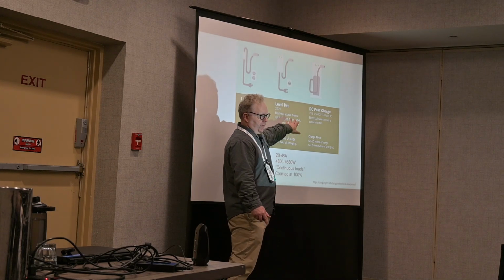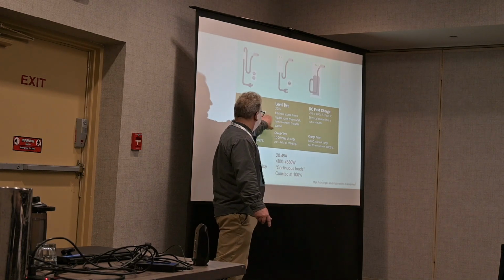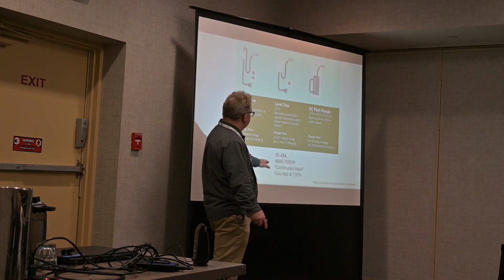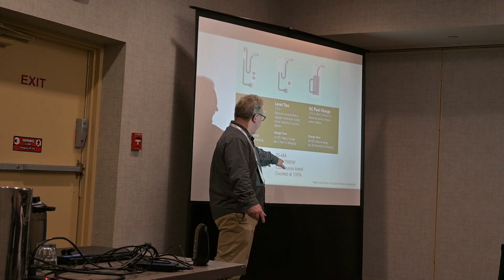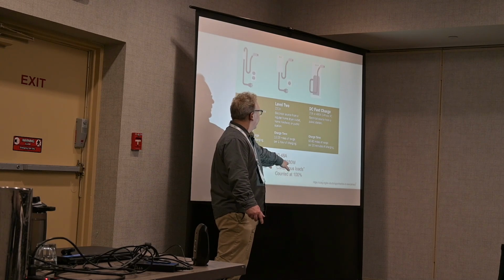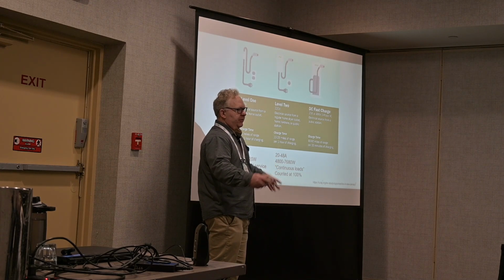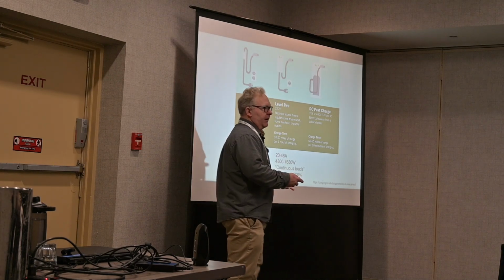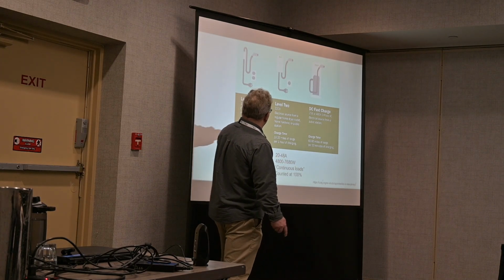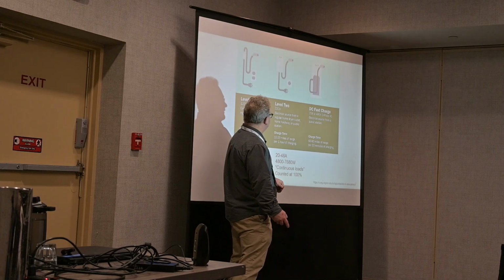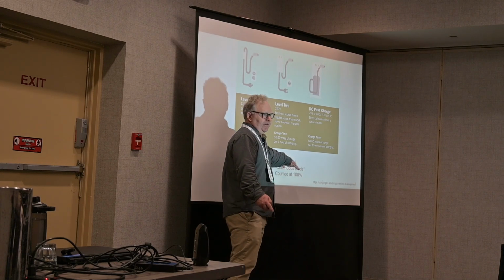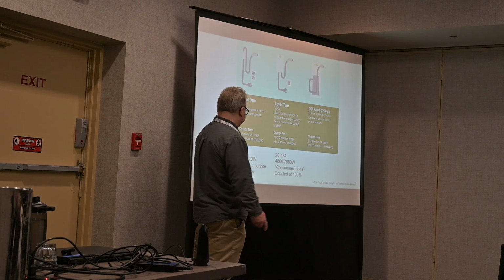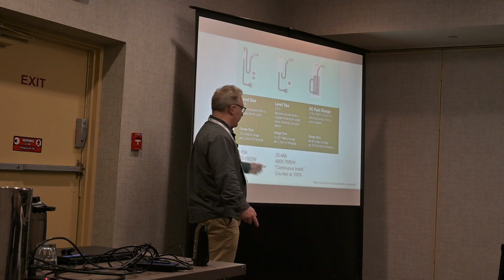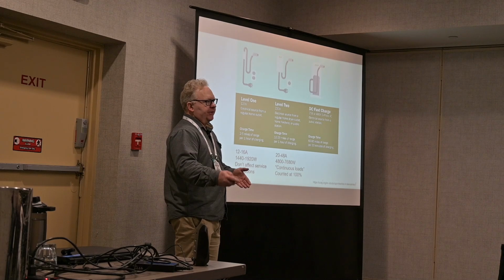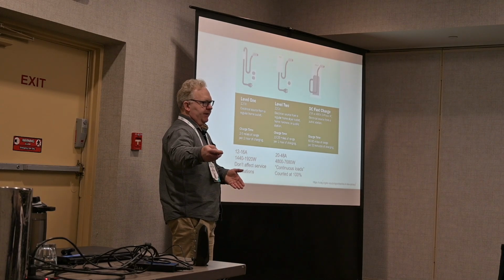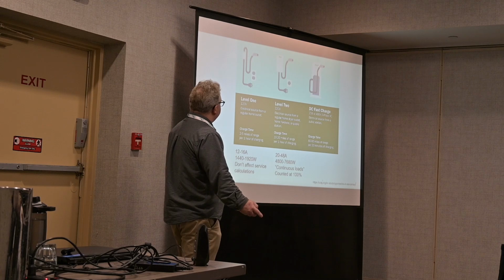Level 2 chargers require dedicated circuits. They're 240 volt. The more amps you set these up with, the faster your vehicle is going to charge. So especially if you're driving a larger vehicle, a pickup, for example, you're going to want a larger level 2 charger. These can add significant draws to the home. They're also considered continuous loads, so they need to be counted at 100%. You don't get to derate them the way that you do appliances.